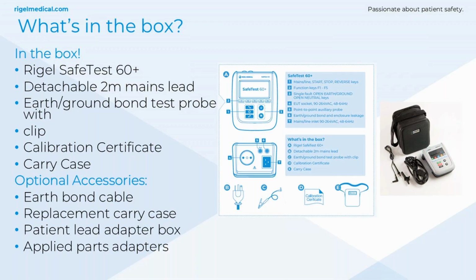We've got a patient lead adapter box, and with NFPA 99 and all of the leads being common to the patient leads, that means you can actually stack the patient lead boxes together. So if you need up to 20 leads, then all you need to do is have 2 patient lead adapter boxes, and they can stack on top of each other. So you're capable of testing up to 20, 30 leads with this device.